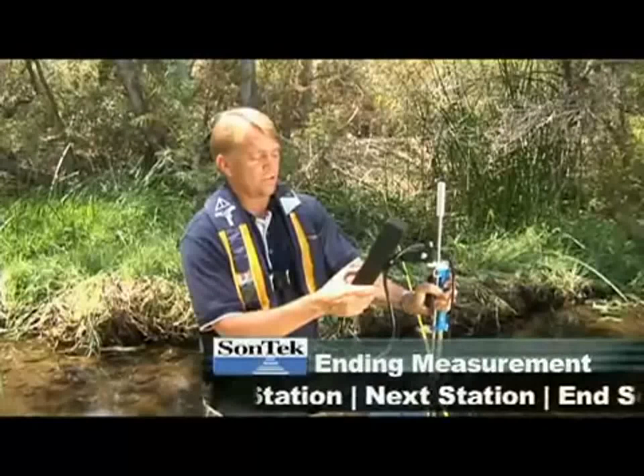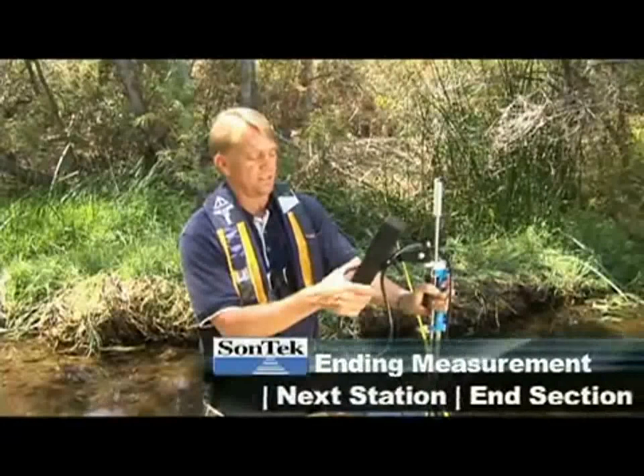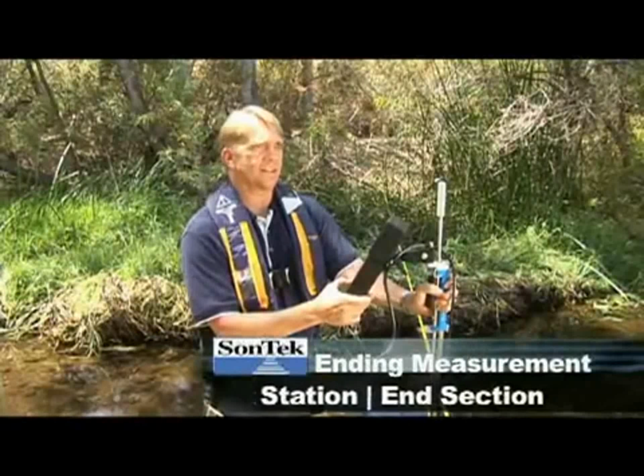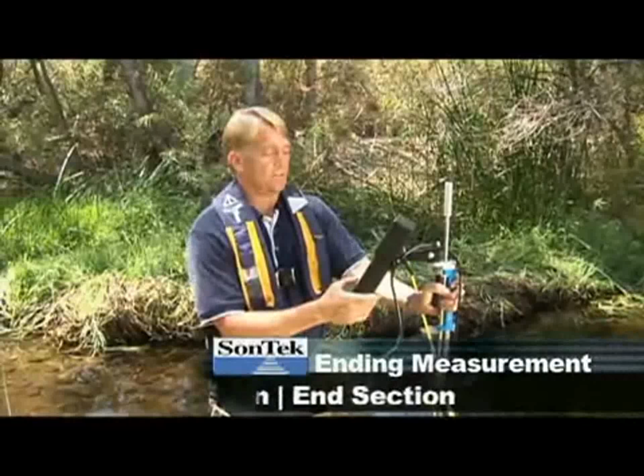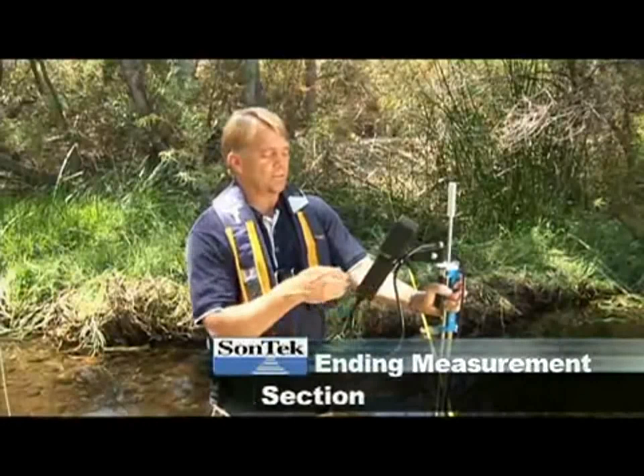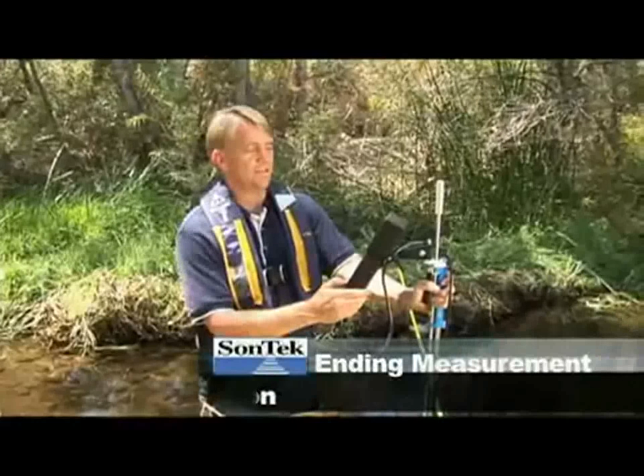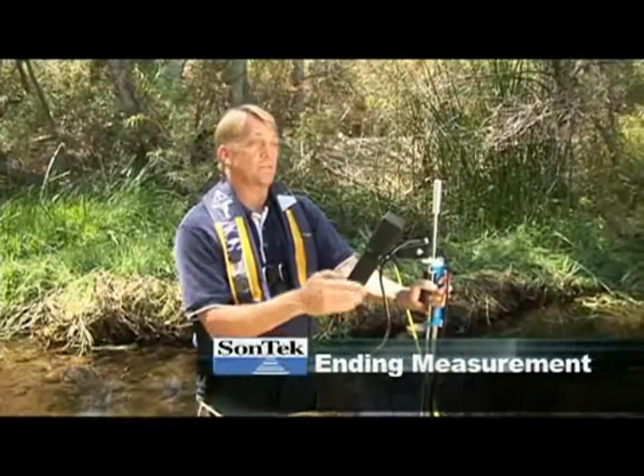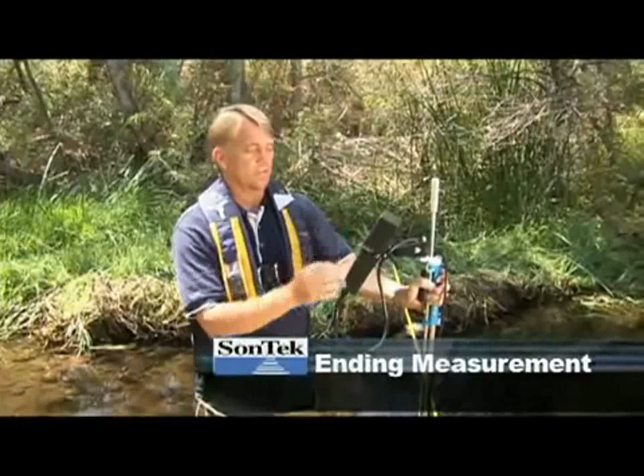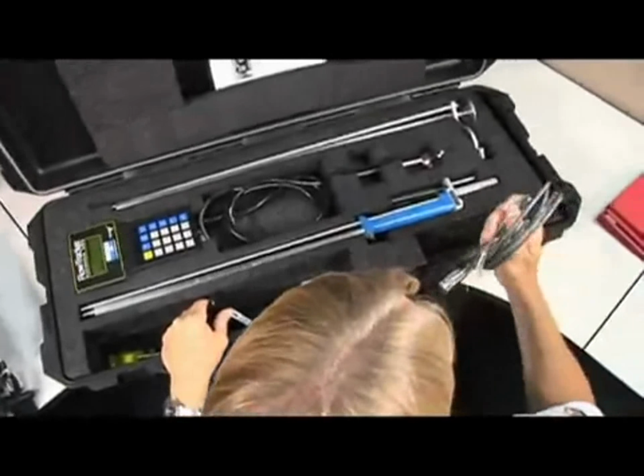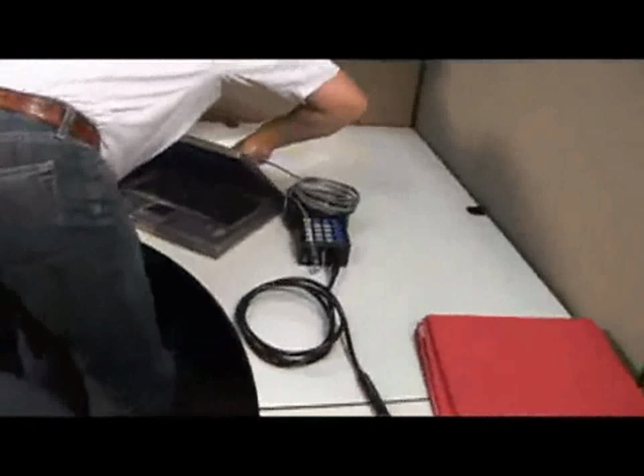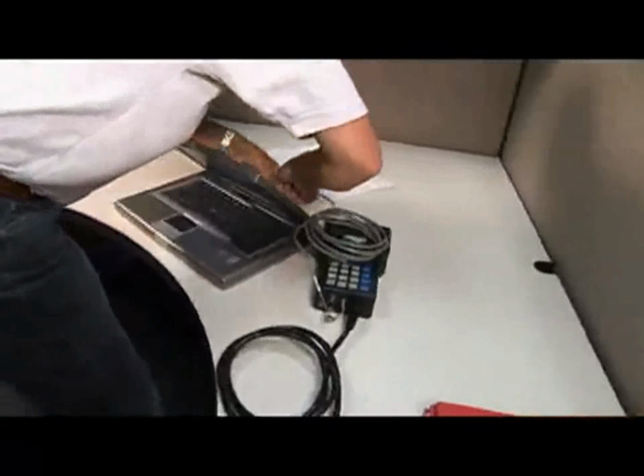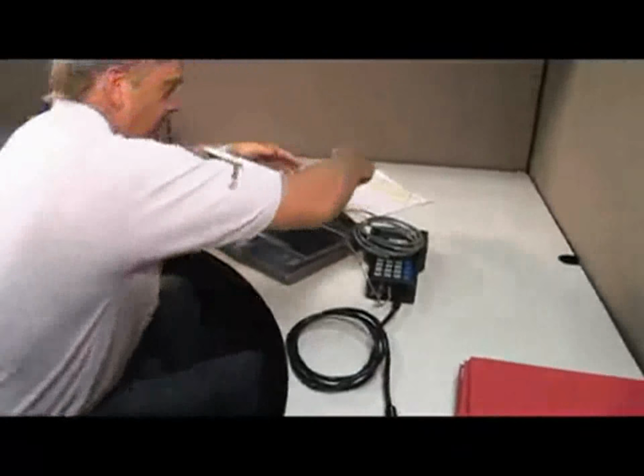So I've done the review by pressing previous station and next station. Things look good, and so I calculate discharge. At this point, it's going to bring up some quality parameters, and basically the results of my measurement. My measurement is complete, and my results are displayed on the screen. After the data has been collected, we connect the FlowTracker to our PC with the serial cable provided. Then we use the FlowTracker software to download the data to our computer.